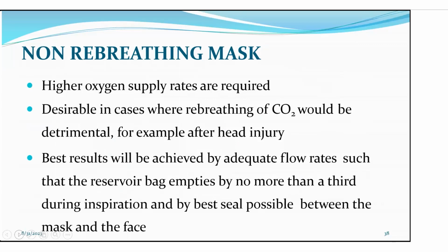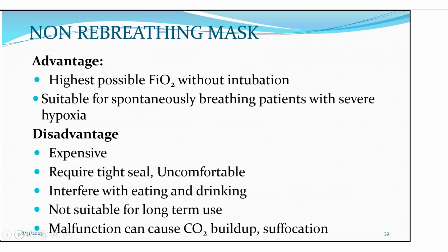The advantages: high oxygen supply rates are required, and it is desirable in cases where rebreathing of CO2 would be detrimental, for example, after head injury. Best results will be achieved by adequate flow rates, such that the reservoir bag empties by no more than a third during inspiration, and by the best seal possible between the mask and the face. The advantage is the highest possible fraction of inspired oxygen without intubation, suitable for spontaneously breathing patients with severe hypoxia. Disadvantages: it may be expensive, requires a tight seal, is uncomfortable, interferes with eating and drinking, and is not suitable for long-term use. Malfunction can cause CO2 buildup and suffocation.